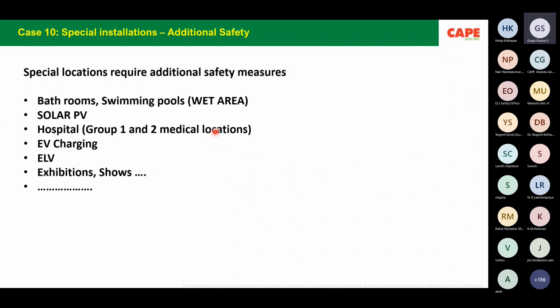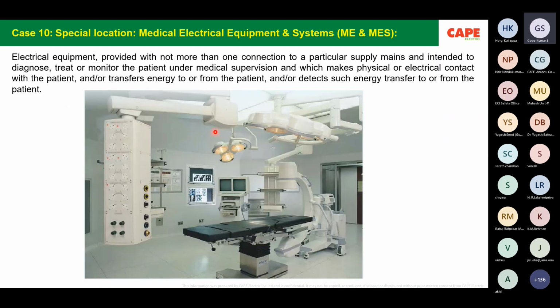As I said, the special installations are bathrooms, swimming pools, solar PV, hospital, EV charging, extra low voltage. Each of these locations requires additional safety measures. For example, in a medical location, supplementary equipotential bonding is required, and touch voltages are reduced to less than 25 volt.